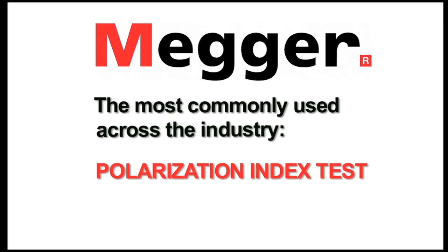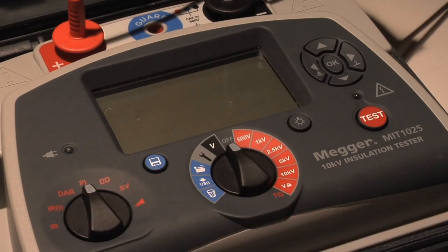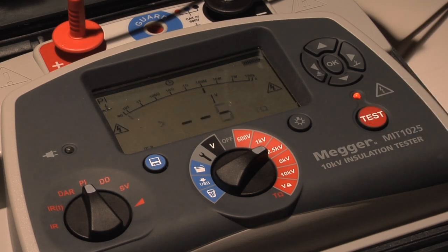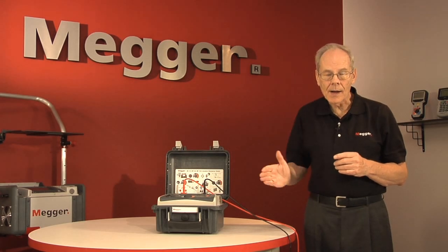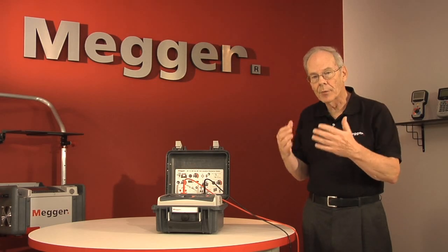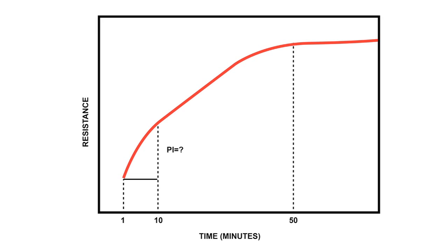The most commonly used test across the industry is the polarization index, which by definition is a one-minute ratio into a ten-minute ratio. The selector switch position goes to PI, you select your test voltage, begin the test, and start making measurements. At the conclusion of the test, the tester will automatically stop, but the critical information will remain on the display. It will show you the resistance reading and leakage current at time one and at time two, which in the case of a PI is ten minutes.